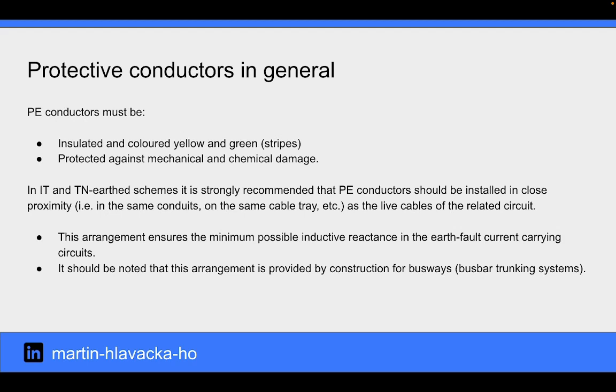PE conductor must be insulated and colored yellow and green, and protected against mechanical and chemical damage. In IT and TN earth schemes, it is strongly recommended that PE conductors should be installed near the live cables of the related circuit. This arrangement ensures the minimum possible inductive reactance in the earth fault current carrying circuits. It should be noted that this arrangement is provided by construction for busbar trunking systems.